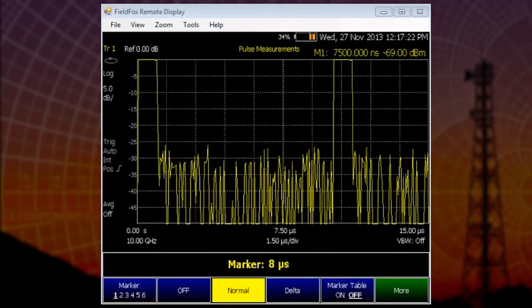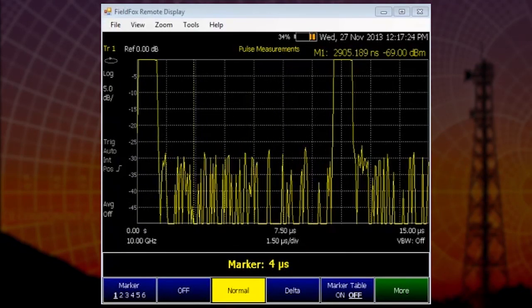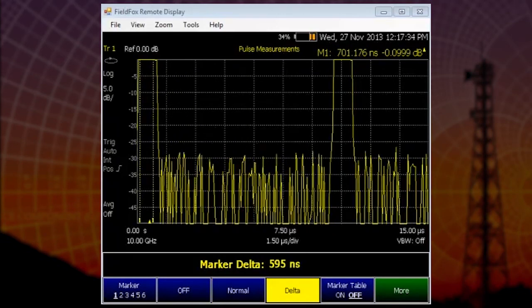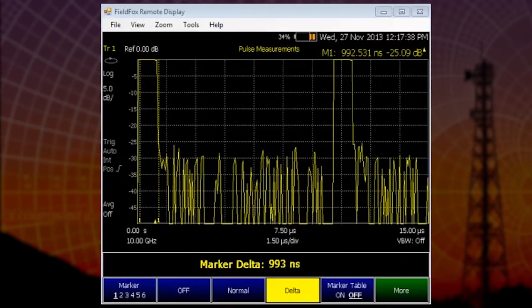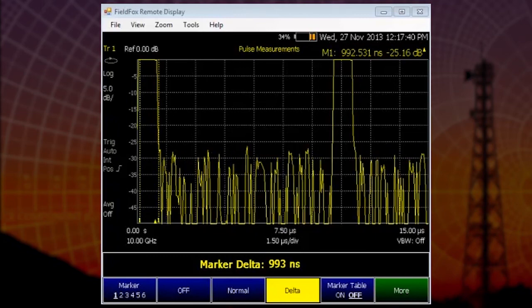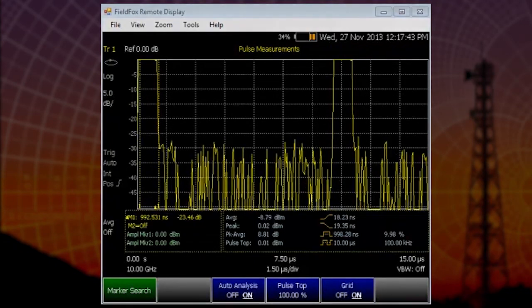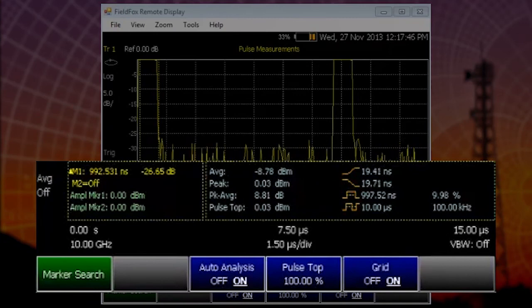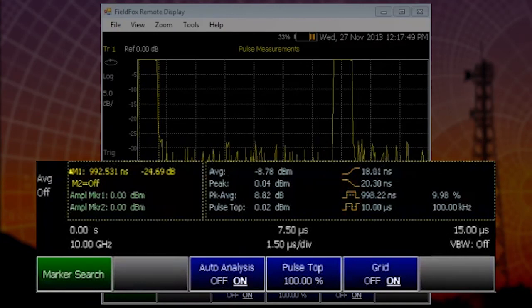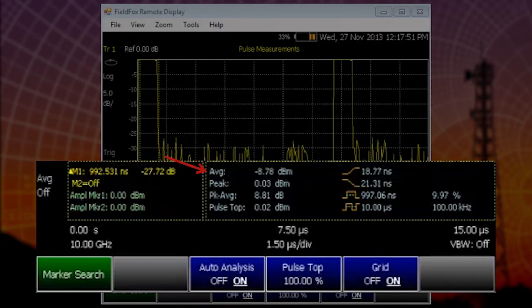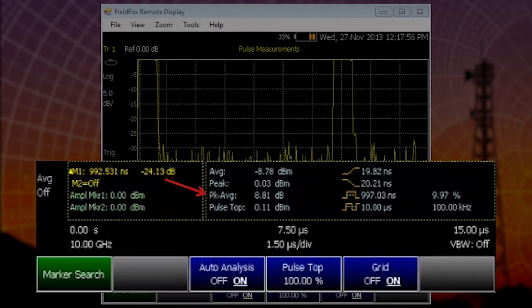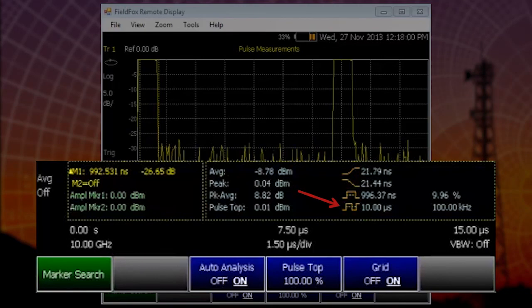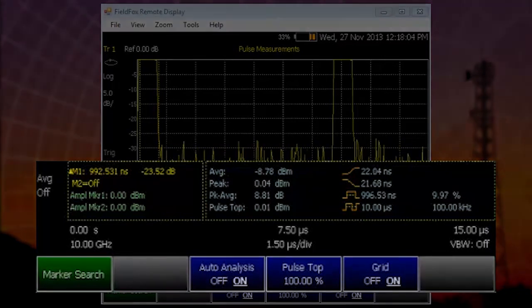Now, we can still make marker measurements of the pulse as we did before, but what I'd like to show you that's even more important is our ability to do auto-analysis. As you'll see, we immediately triggered on the pulse and we're able to now see all the pulse metrics, the average peak, peak to average, the pulse top in amplitude, the pulse width, and the pulse repetition interval, very simply.